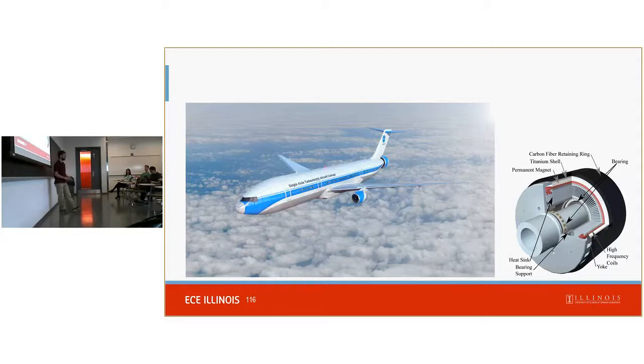Yeah, awesome. What's the full-size motor expected to be? How big is it? The diameter is about 13 inches, and the active length is 9.5. That's a 1 megawatt output. One of the major thrusts of the project is high specific power, and the target is 13 kilowatts per kilogram, which is a lot higher than most.